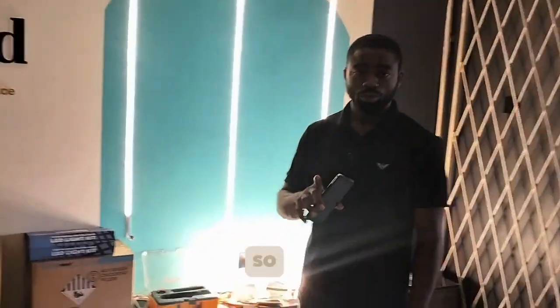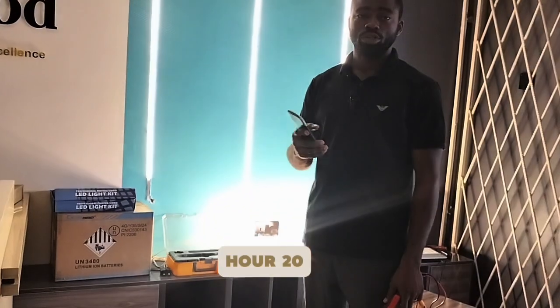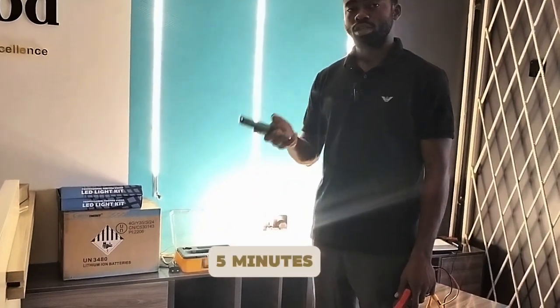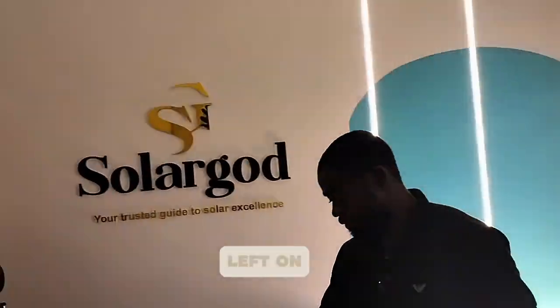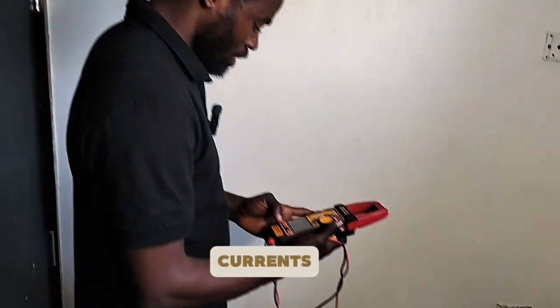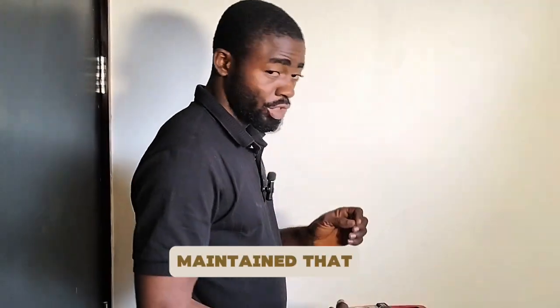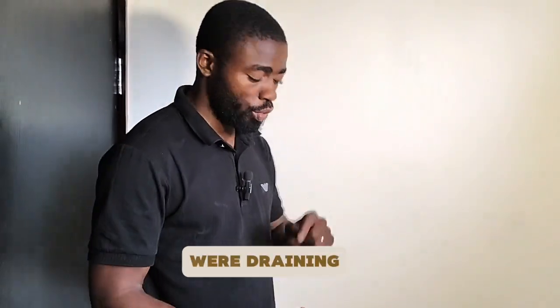The battery has 80% depth of discharge, so it's expected that the battery should give us 3 hours 30 minutes or 3 hours 20 minutes. So it's already 3 hours 5 minutes or 3 hours 6 minutes. We've maintained the same load and the inverter is still running. So let's check out the voltage that is left on each battery. I'll still check out the current to see if we have actually maintained that 5 amps which we were draining earlier.